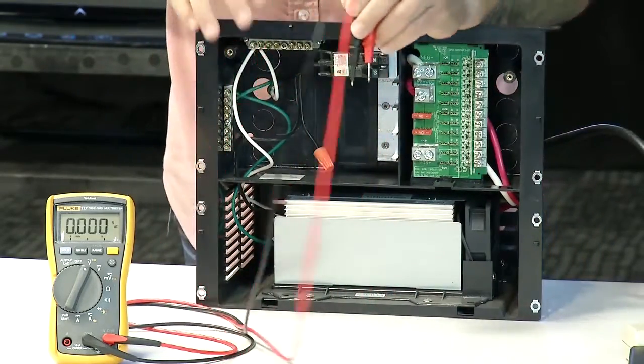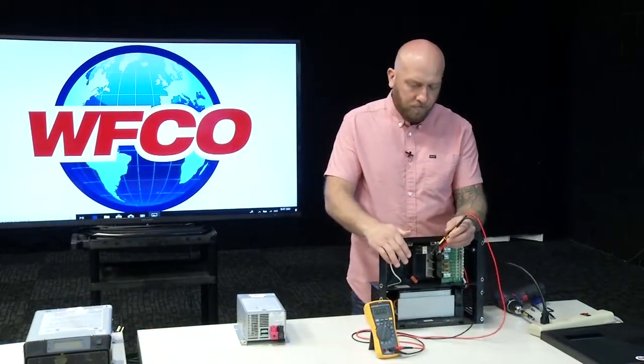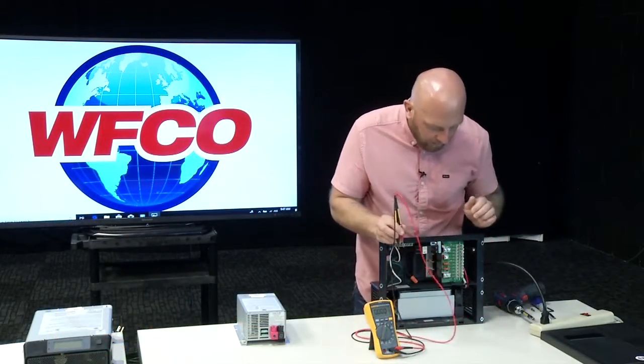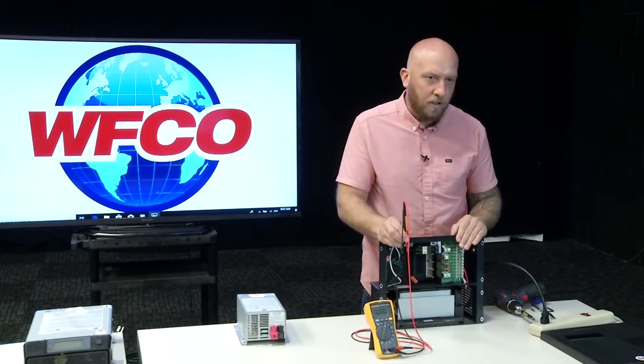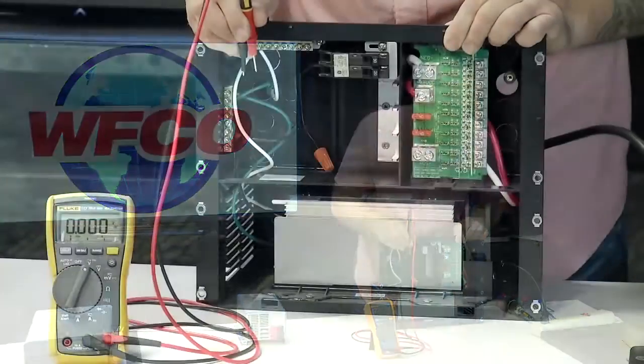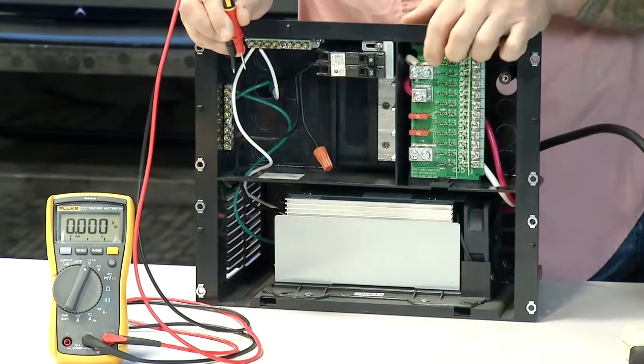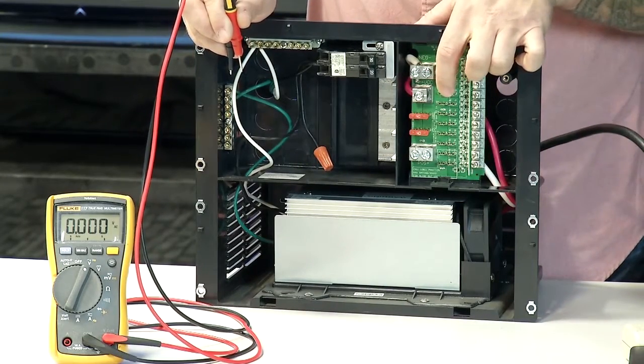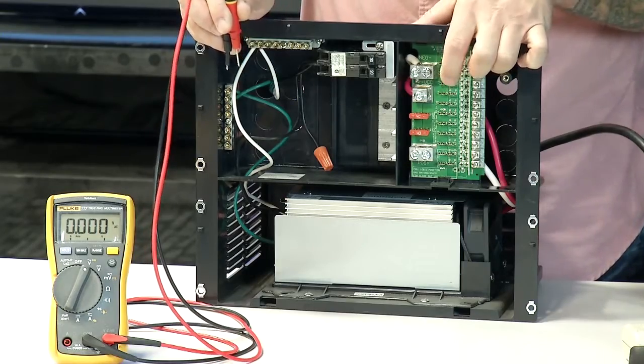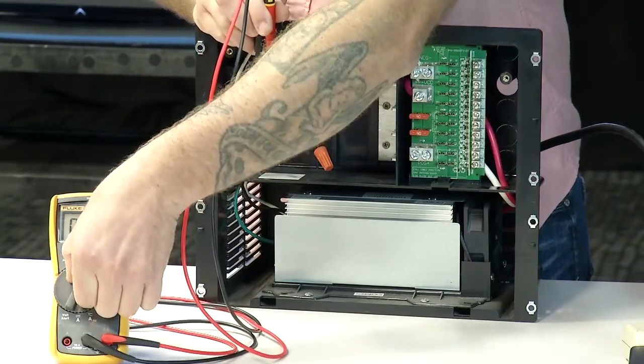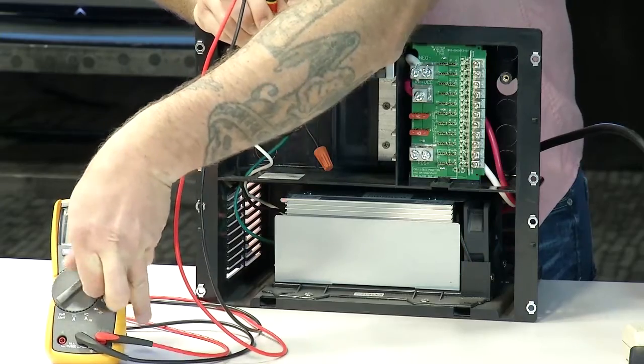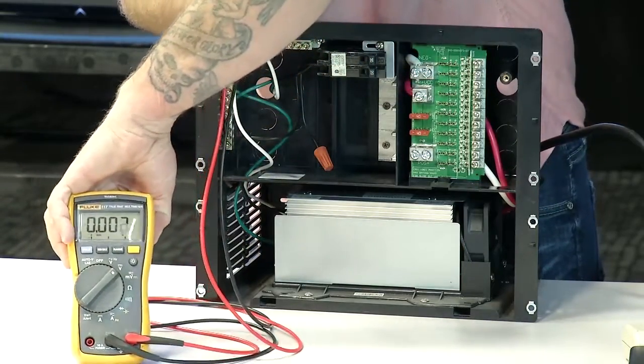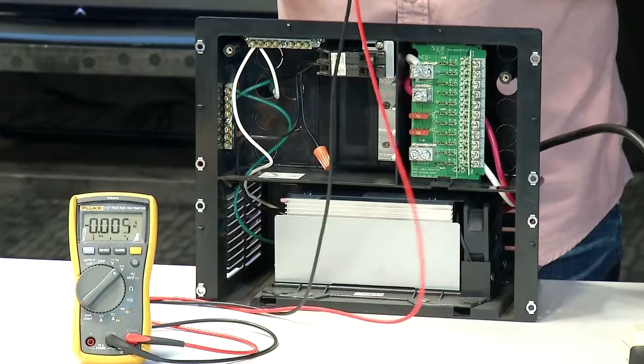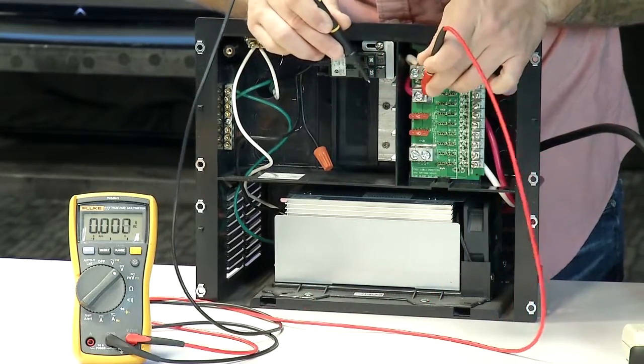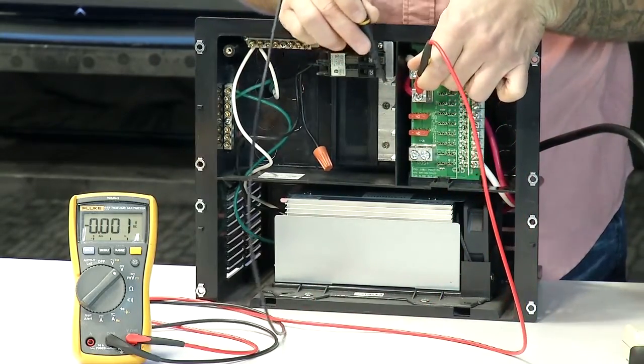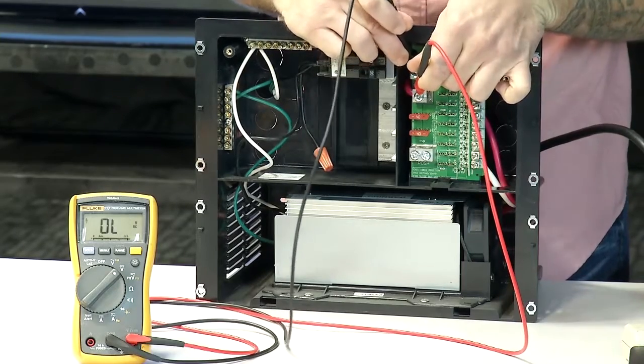Once you have verified you have good AC voltage coming in, we're going to go to the DC side of the converter itself over here, which is our fuse board. As you can see right here, we have our neutral coming in, and right below is our AC hot, so the red and white wire. So you're going to turn your meter to DC volts. And you're going to check between the red wire, which is your hot, and the white, which is your negative.